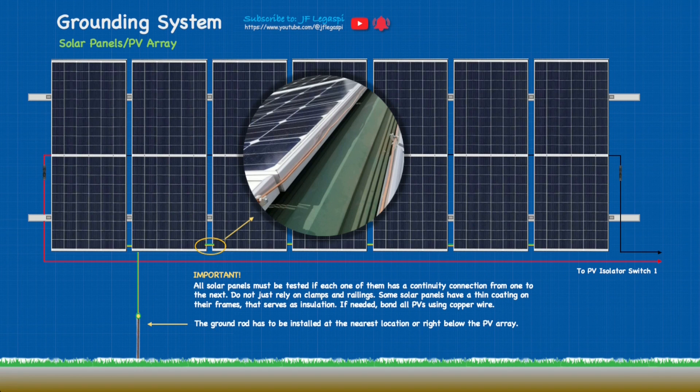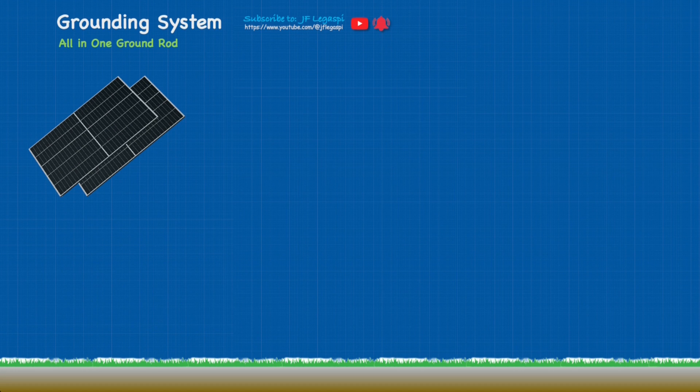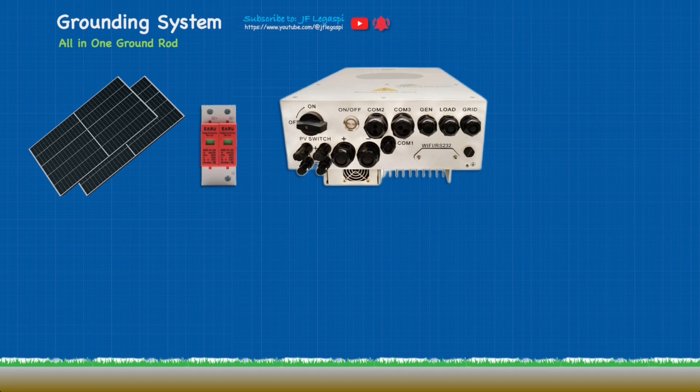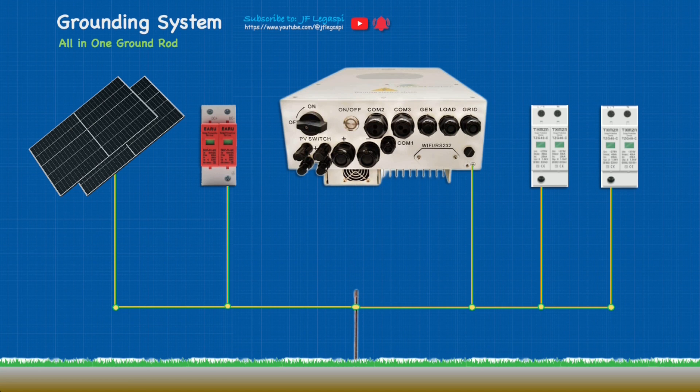The next important thing is the ground rod has to be installed at the nearest location or right below the PV array. And now let's take a look at all-in-one ground rod. Okay, we have the PV array, the DC SPD, of course we have our hybrid inverter, the AC SPD on the AC output of our hybrid inverter, and another one for the AC input of the hybrid inverter. So we can just have one ground rod and connect all of this into that.